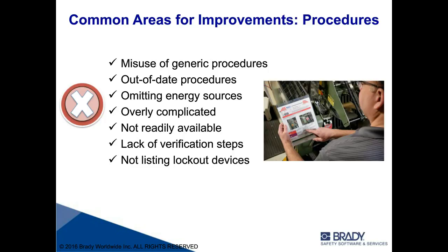Not readily available. The most important people that should have those procedures are the operators themselves, or the mechanics doing the work, especially those authorized for Lockout Tagout. Lack of verification steps: outside of not actually doing Lockout Tagout, the verification step is important because most people don't verify that what they shut off is actually turned off. Then someone's working on a piece of equipment, someone hits the start button or it inadvertently starts, and they get injured. And then not listing Lockout Tagout devices - how do you specifically lock something out, especially with something that doesn't accept a lock, a tag, or a hasp directly?